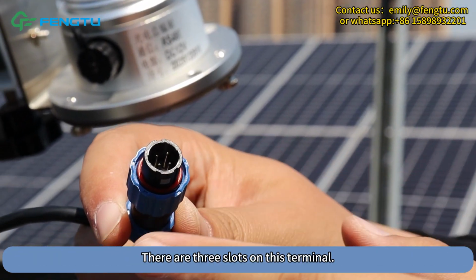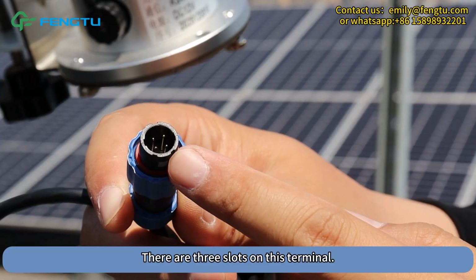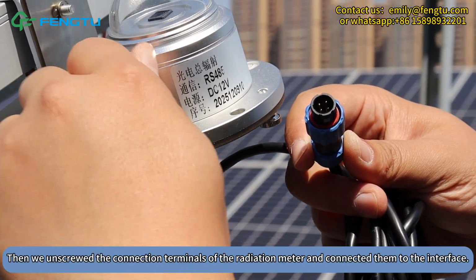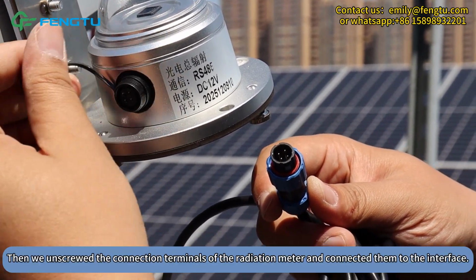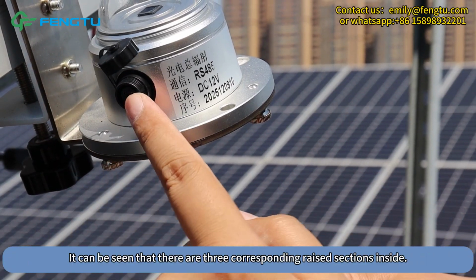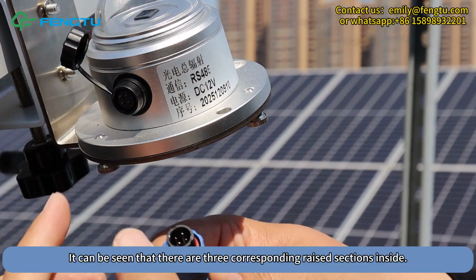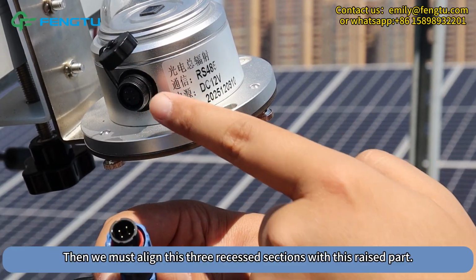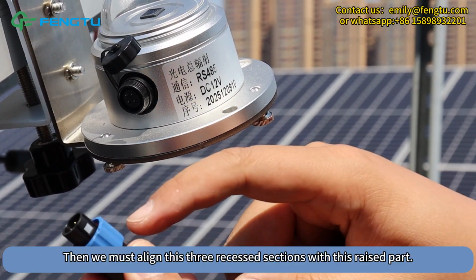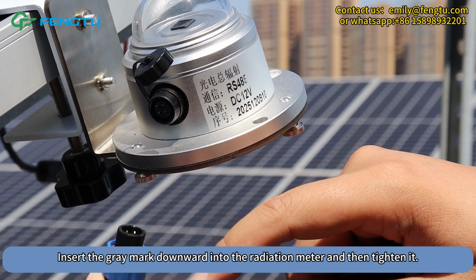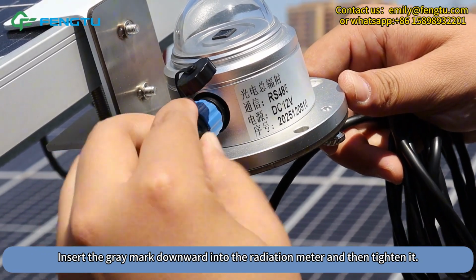There are 3 slots on this terminal. Then we unscrewed the connection terminals of the radiation meter and connected them to the interface. There are 3 corresponding raised sections inside, so we must align these 3 recessed sections with the raised part. Insert the gray mark downward into the radiation meter and then tighten it.